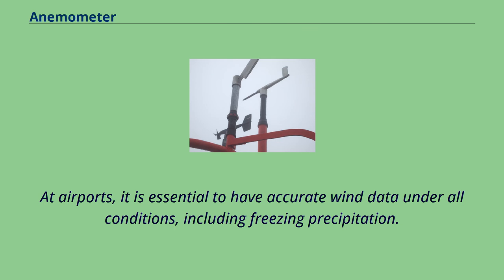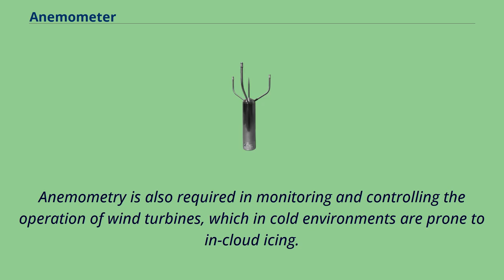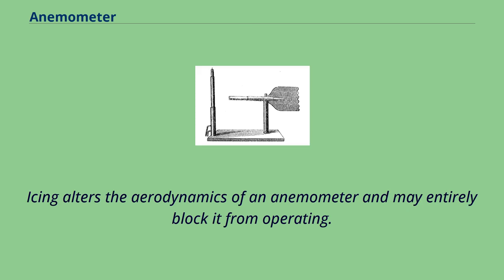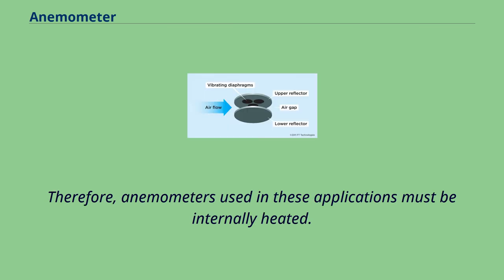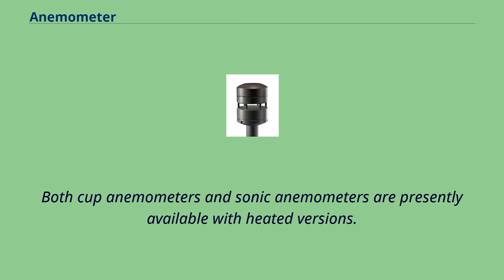At airports, it is essential to have accurate wind data under all conditions, including freezing precipitation. Anemometry is also required in monitoring and controlling the operation of wind turbines, which in cold environments are prone to in-cloud icing. Icing alters the aerodynamics of an anemometer and may entirely block it from operating. Therefore, anemometers used in these applications must be internally heated. Both cup anemometers and sonic anemometers are presently available with heated versions.